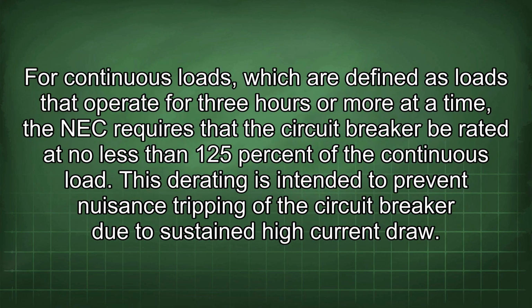For continuous loads, which are defined as loads that operate for 3 hours or more at a time, the NEC requires that the circuit breaker be rated at no less than 125% of the continuous load. This derating is intended to prevent nuisance tripping of the circuit breaker due to sustained high current draw.